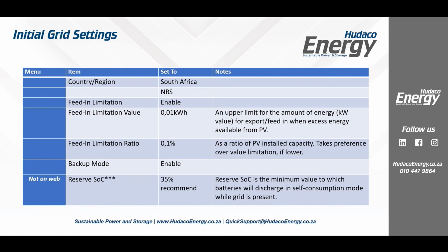Backup mode, you set to enable, and then reserve state of charge. You can choose what it is for your client. I've just put 35% there as a recommended amount. If it's in the middle of a load shedding season, you could set that to 40 or 50 or 60% if you wanted to. And we'll explain what each of these means in a little bit. We've got a lot of clients that say, well, 35% should be good to start, or 40% or 50%. By the end of today, you'll be able to select that one as you like. So these are your initial grid settings.